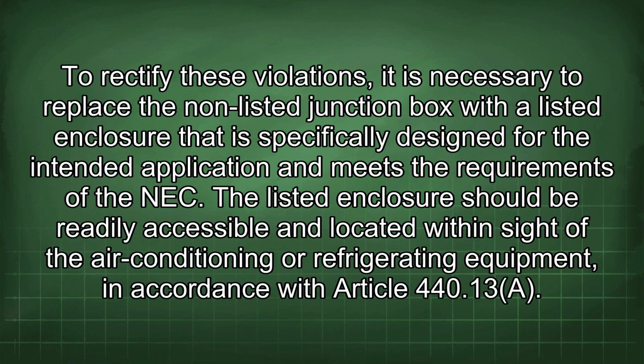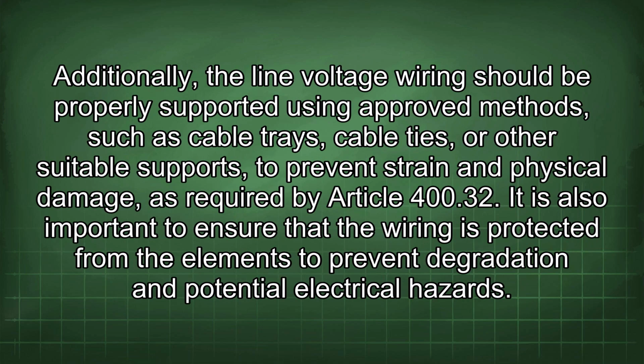To rectify these violations, it is necessary to replace the non-listed junction box with a listed enclosure that is specifically designed for the intended application and meets the requirements of the NEC. The listed enclosure should be readily accessible and located within sight of the air conditioning or refrigerating equipment, in accordance with Article 440.13(A). Additionally, the line voltage wiring should be properly supported using approved methods, such as cable trays, cable ties, or other suitable supports, to prevent strain and physical damage, as required by Article 400.32.